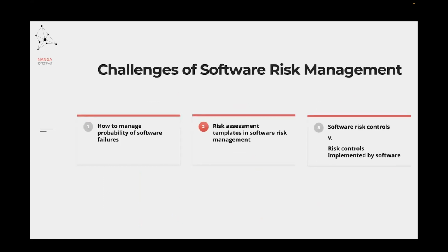This covers the quick overview of the software safety classification. Now let's move on to software risk management, where we have three main challenges that we might face during our risk management activities. The first one is how to manage probability of software failure. We briefly touched on this before, but we will get back to this topic a little bit later. Then there are risk assessment templates in software risk management: if they are applicable, or how should we apply these templates to software, because typically these are non-software related risk management templates, for example, ISO 14971.